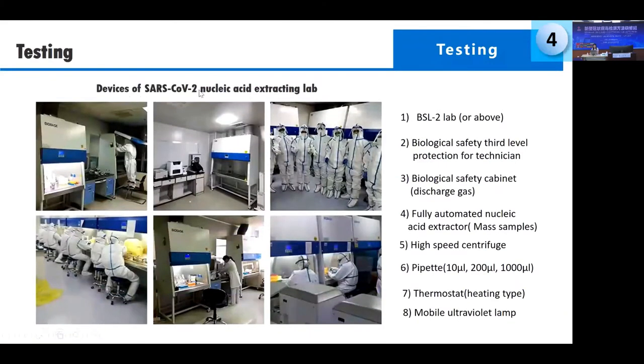For the SARS-CoV-2 nucleic acid extraction lab, we need a BSL-2 or BSL-3 laboratory with biological safety level 3 protection for technicians, and a biological safety cabinet with exhaust gas discharge. A fully automated nucleic acid extractor is used for mass samples. We also need a high-speed centrifuge, pipettes of 10, 200, and 1000 microliters, a thermal block for heating, and a mobile ultraviolet lamp for disinfection.